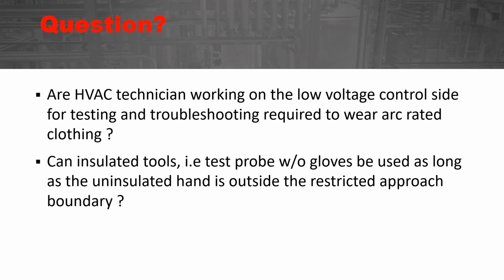Also, 70E has a definition of working on. The definition of working on energized electrical conductors and circuit parts in Article 100 of 70E says that someone is intentionally coming in contact with energized electrical conductors and circuit parts with the hands, feet, or other body parts, with, and this is the important part, with tools, probes, or test instrument, regardless of the personal protective equipment. So even if you're holding probes, you are working on the equipment. And just where is the restricted approach boundary? Where is the arc flash boundary? All of that is important.